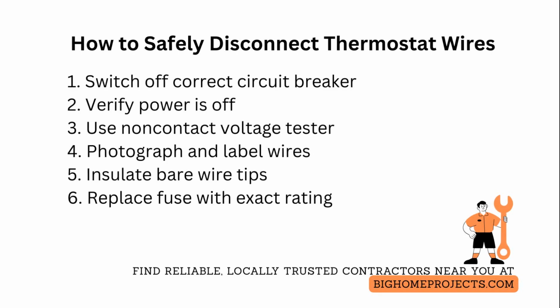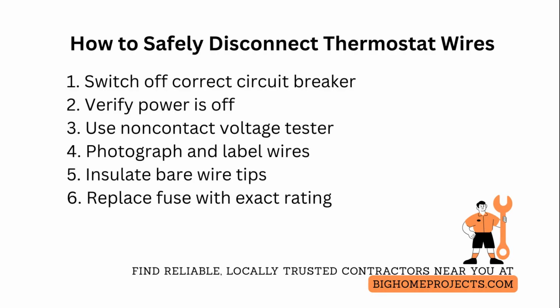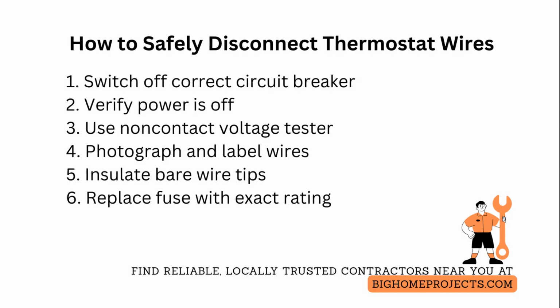Use a non-contact voltage tester on the thermostat wires and at the furnace control terminals to confirm no voltage is present before you touch or disconnect anything. Never rely only on the thermostat display going dark, because some smart thermostats have battery backup.